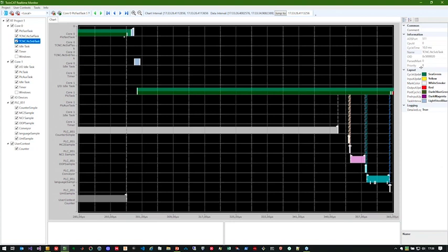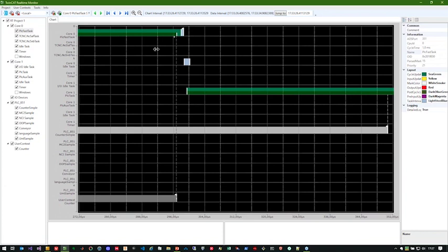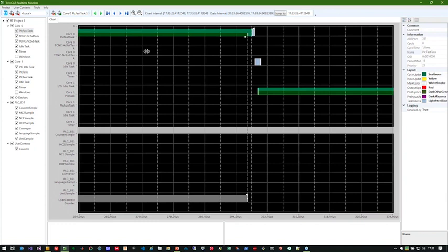The priority of this is 8. The cycle time is 10 milliseconds. For the fast task of the PLC, the cycle time is 1 millisecond, and the priority 21. And this means if you do an analysis later on, you will see that on each 10th execution, you may have a cycle time exceeding of the PLC fast task. This is also what you would like to see here.